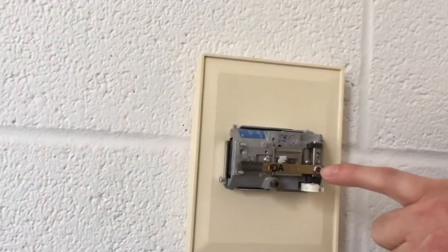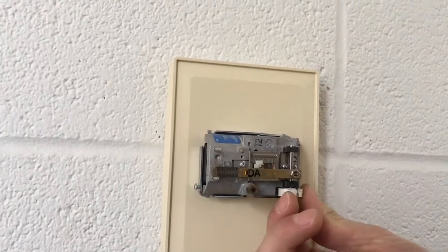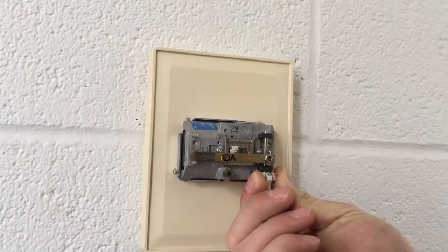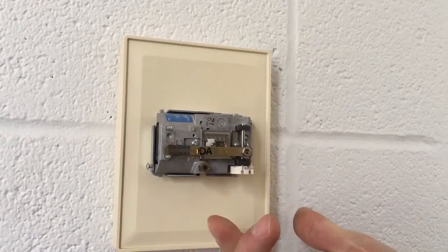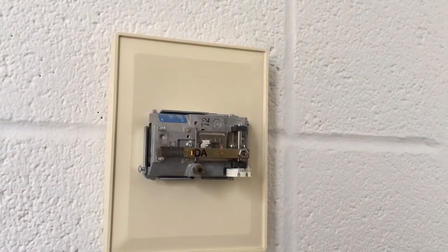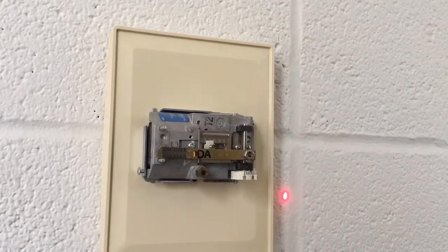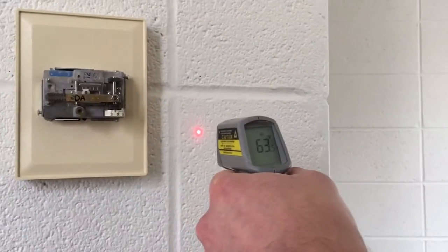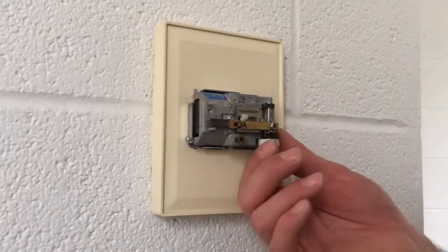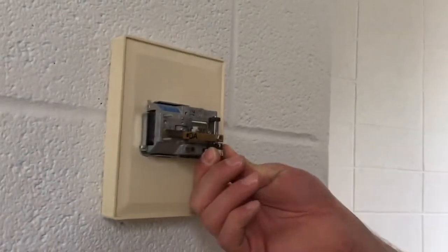After checking those two things, the next thing I check is whether the thermostat's calibrated to the right temperature or not. If you look at the thermostat itself, this screw at the end changes your set point calibration. So if you turn this dial, when it starts to vent air, that's the temperature it thinks the space is at. So this one thinks the space is about 58 degrees or so. We're actually about 63 on the wall surface. The air temperature is probably a couple of degrees cooler. So it's safe to assume it's probably a little bit out of calibration.